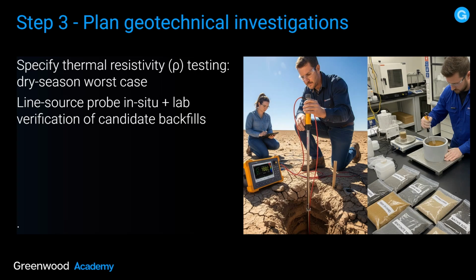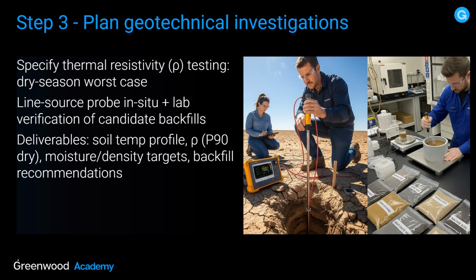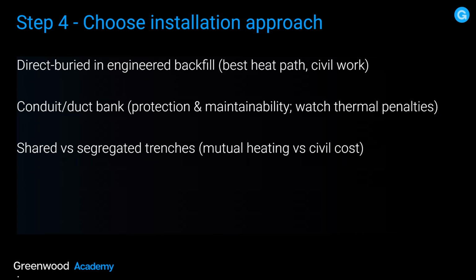So really make sure that your geotech guys or the company that you employ do the right job, do a thorough investigation, make sure they take lots of core samples. Line source probe, in situ and lab verification of the candidate backfills. The deliverables have to be the soil temp profile, the thermal resistivity, moisture, density targets, backfill recommendations if required. Step 4, choose installation approach.